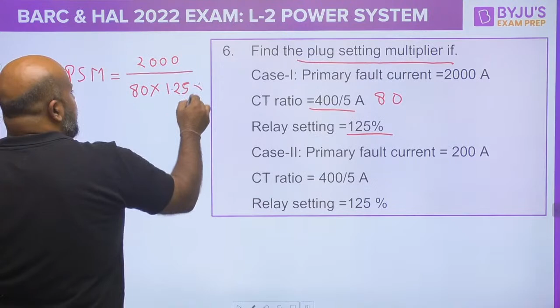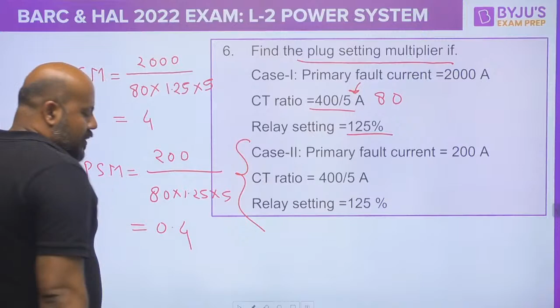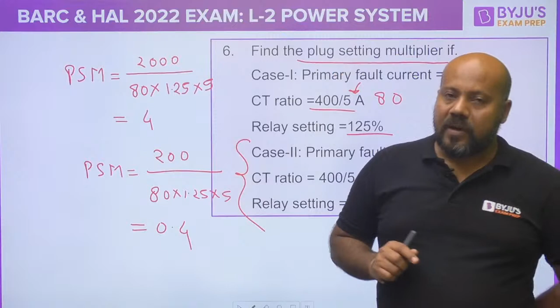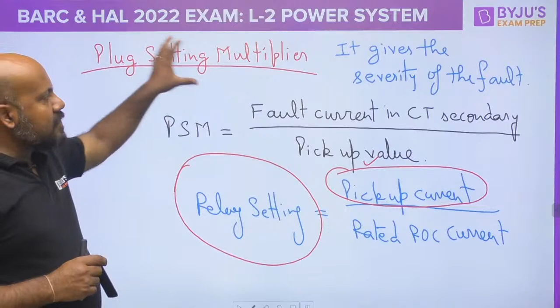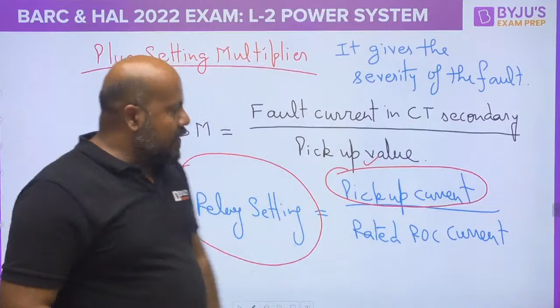Is it clear for everybody? Just tell me in the comment section. Now it is very easy to find the solution. You have to find the plug setting multiplier. Fault current in the CT primary is 2000 amperes, divided by the CT ratio. If you solve it, it is going to be 80. Yes or no? More than 1 you have to write. Just write 80 here. What is the relay setting? 125, so this is going to be 1.25. What is the rated RoC current? Rated RoC current is the secondary CT rated current, that is 5. So it is going to be 5. If you solve this, you will get 4.